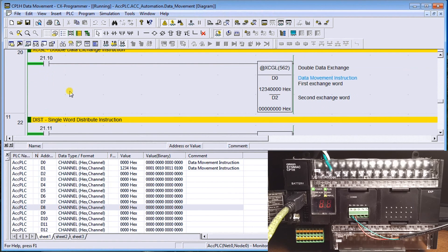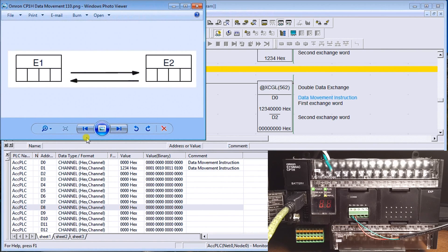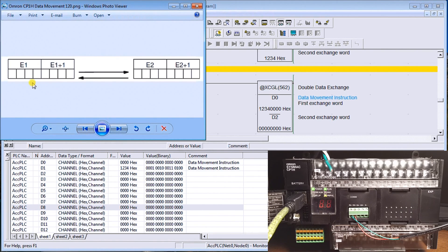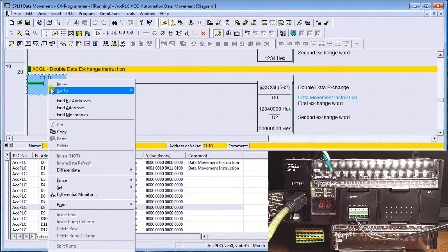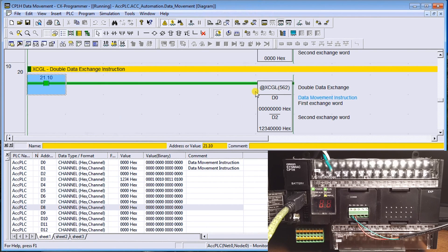Next is Double Exchange (XCGL). It takes two words at a time — a double word — and swaps it with another double word. Turning it on, the values in D0 and D1 move to D2 and D3, and the values from D2 and D3 go to D0 and D1. Again the @ sign is used to pick up the transition from off to on as a one-shot.